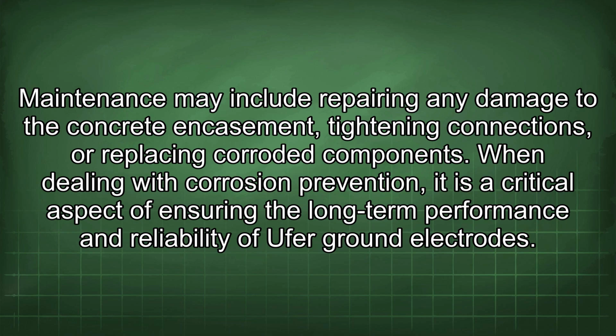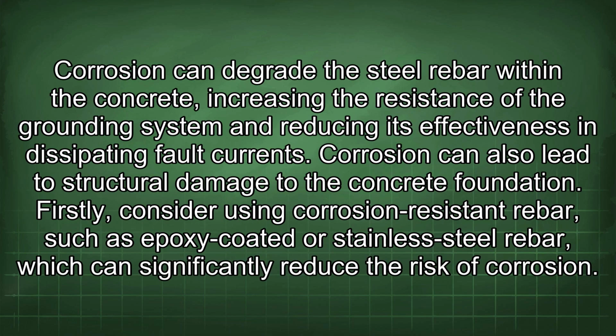Corrosion prevention is a critical aspect of ensuring the long-term performance and reliability of Ufer ground electrodes. Corrosion can degrade the steel rebar within the concrete, increasing the resistance of the grounding system and reducing its effectiveness in dissipating fault currents. Corrosion can also lead to structural damage to the concrete foundation.